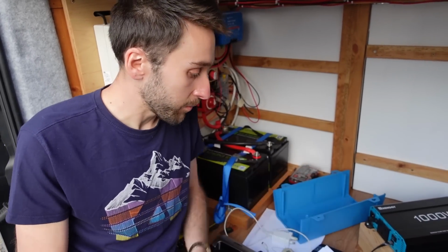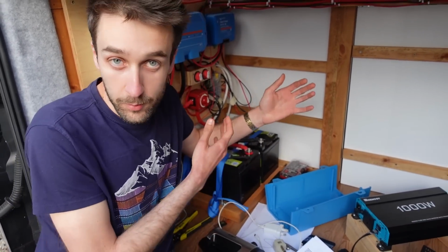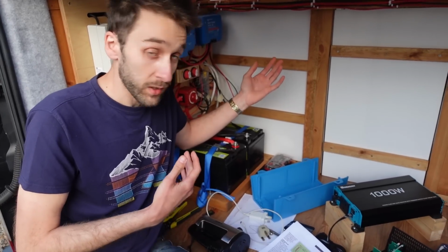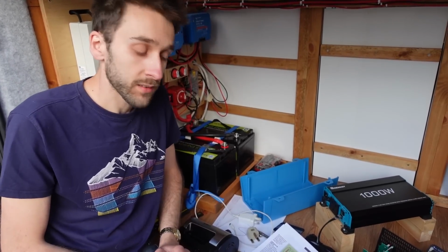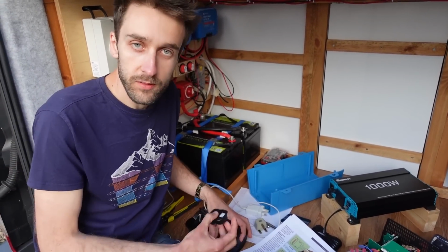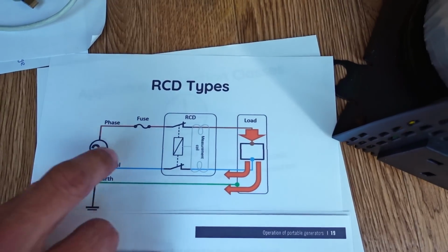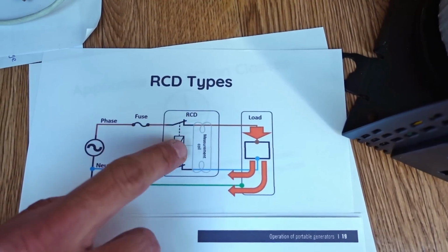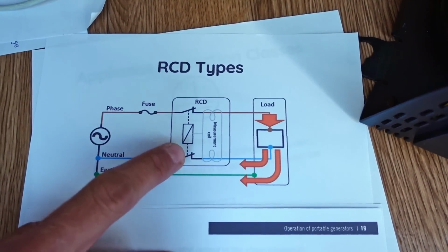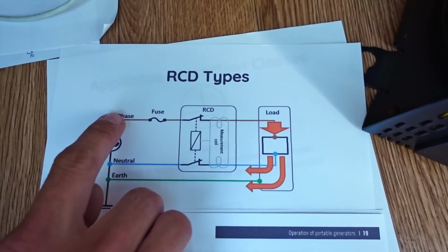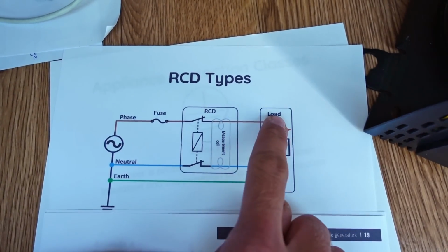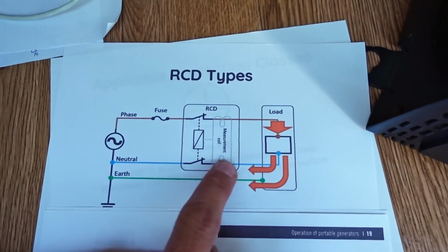We definitely want to have that kind of setup, because we're going to have multiple sockets in the van, so we could in theory be plugging in multiple appliances at the same time without knowing exactly what classes they'll be. An RCD is just a little device that sits between the live and neutral wires, constantly checking that the amount of current going out on the live is exactly the same as what comes back on the neutral.